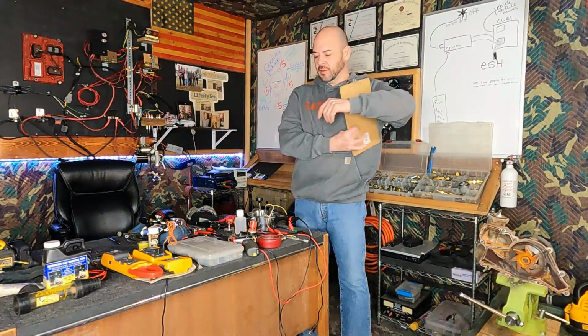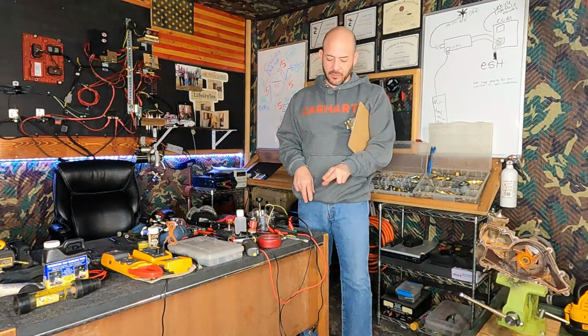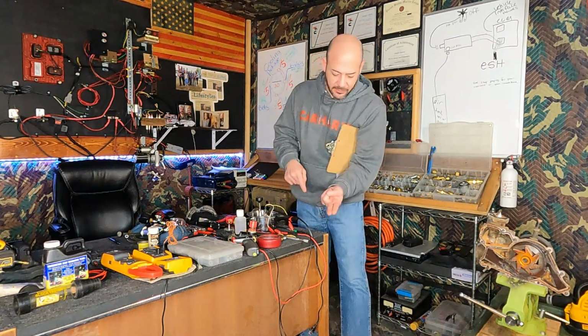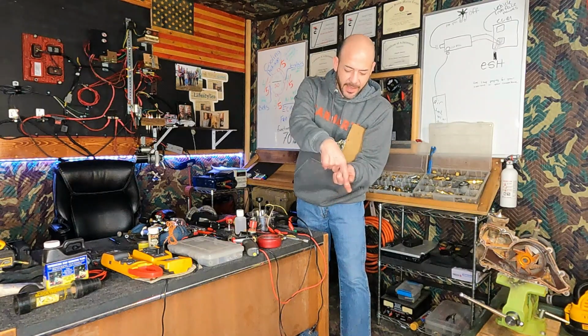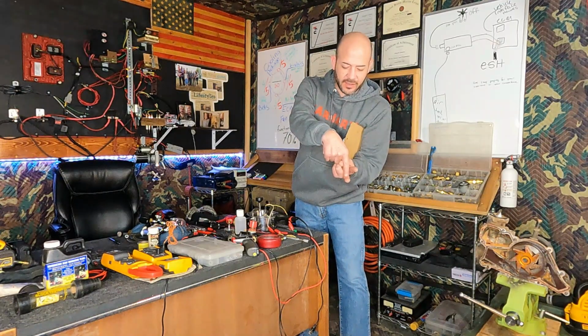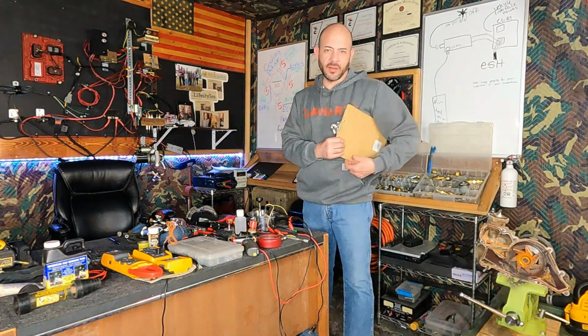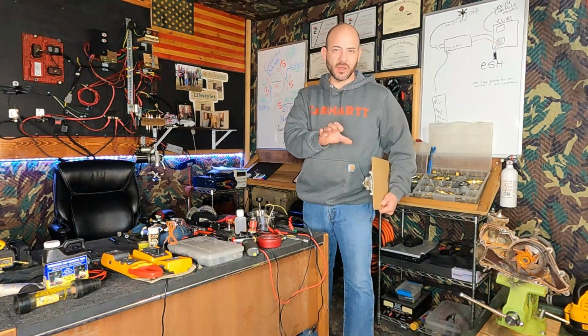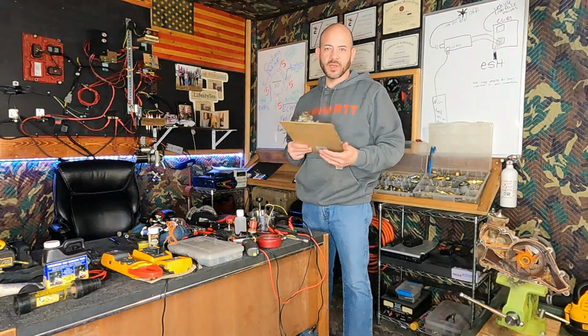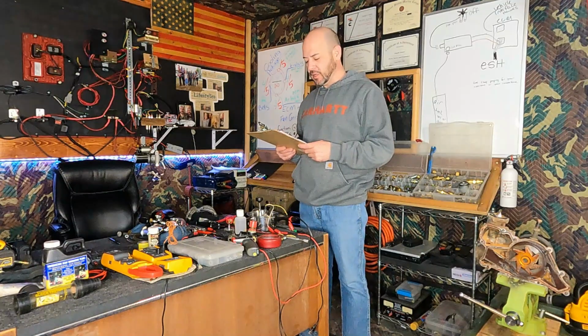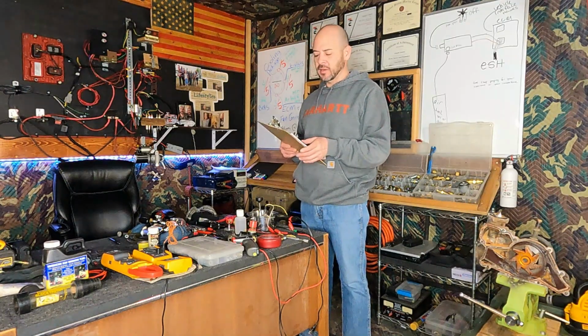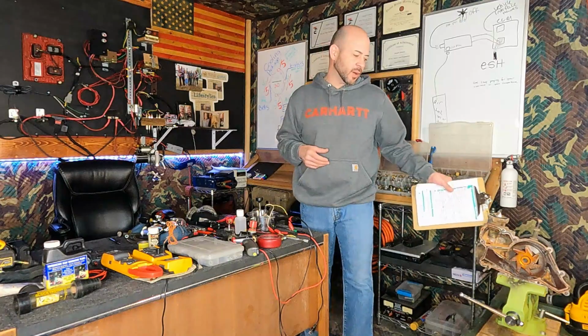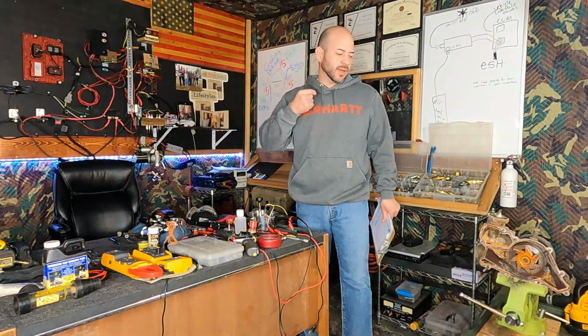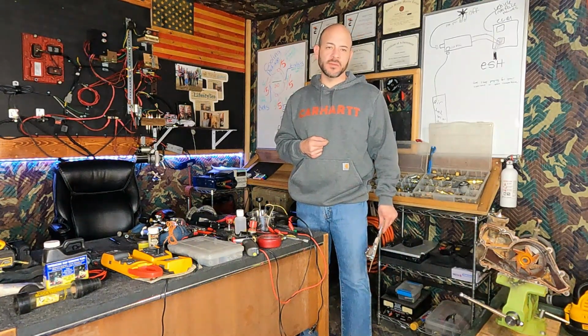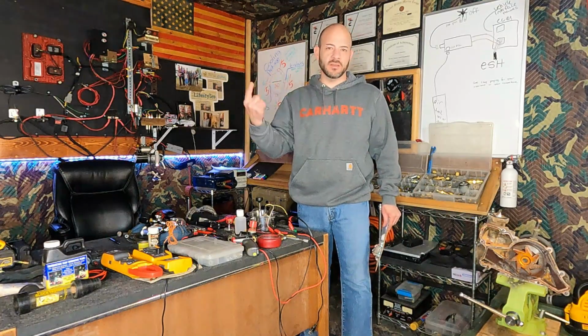And if you have a V-belt setup, let's say you have 2 belts sitting next to each other like this, I push down on this one, that belt shouldn't go past that first indentation or a certain amount of foot-pounds, and they have belt tension gauges that will tell you how much foot-pounds of pressure is being applied to that belt. That's really, really important when it comes to cooling things, especially when we're talking about turning that pump. Because if I have slipping on that pump, it's not going to be able to keep up the flow rates to be able to keep that much heat out of the system.